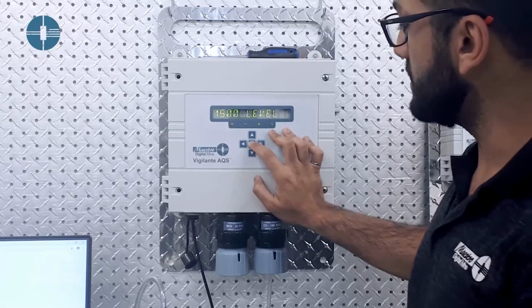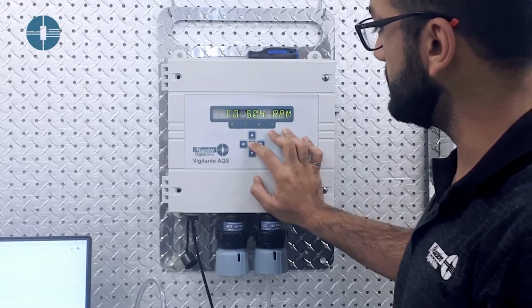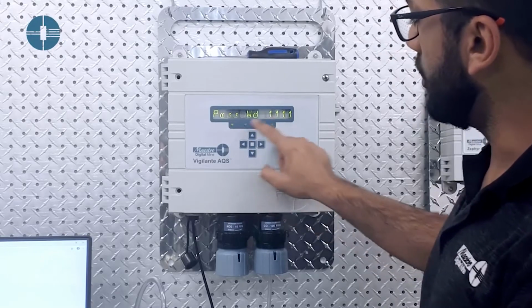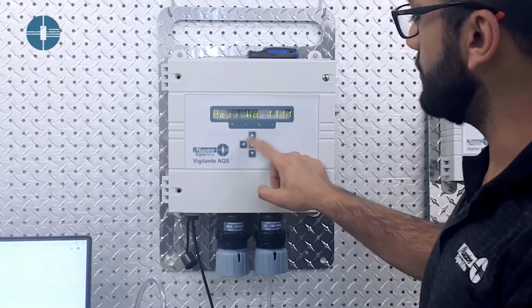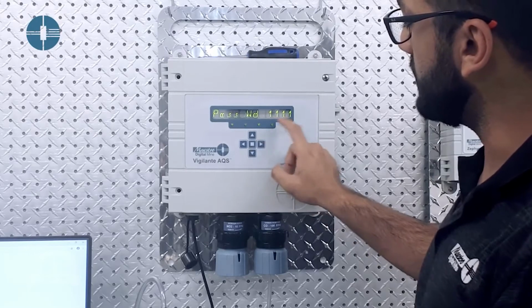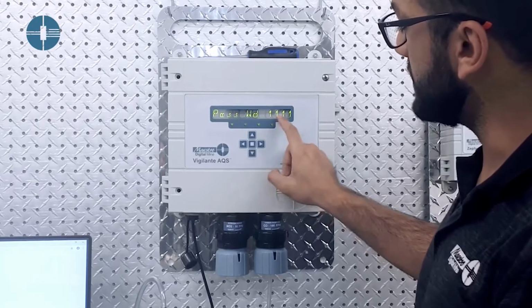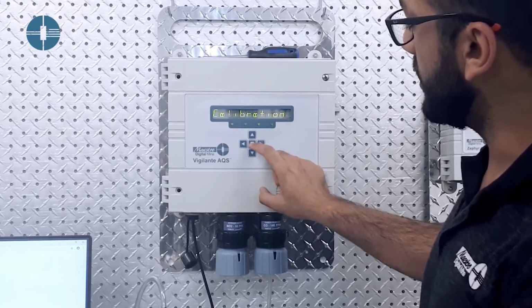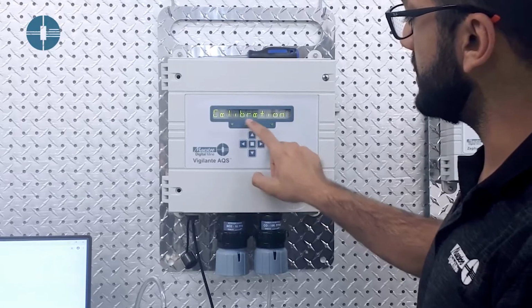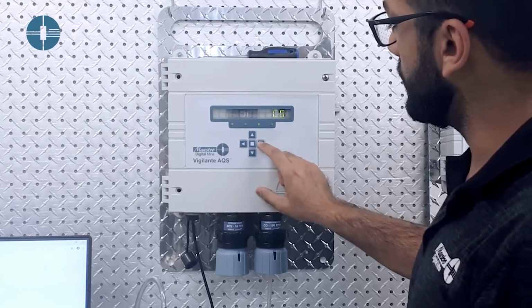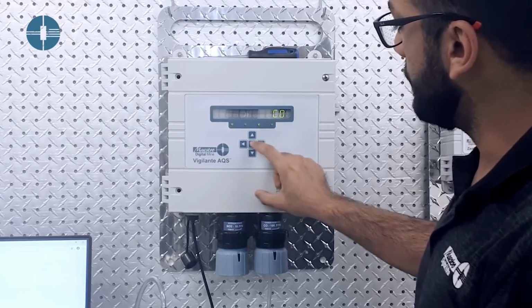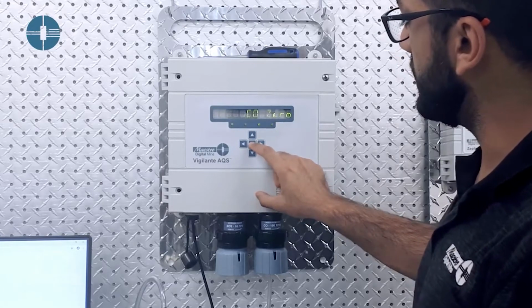So we're going to hold the center button for approximately 6 seconds. And you get prompted with the password. Again, you can use the up, down, right, left arrow to change your password, if you've changed it. That's our default password. You hit OK, which is the center button. You enter your calibration mode. You go to your sensor. Once you get to your specific sensor, you hit OK.